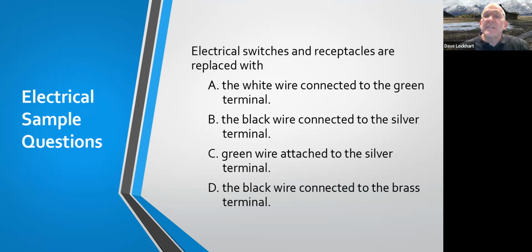Electrical switches and receptacles are replaced with the white wire connected to the green terminal. Okay, so this is the wiring of them. The white wire connected to the green terminal, the black wire connected to the silver terminal, the green wire connected to the silver terminal, or the black wire connected to the brass terminal.